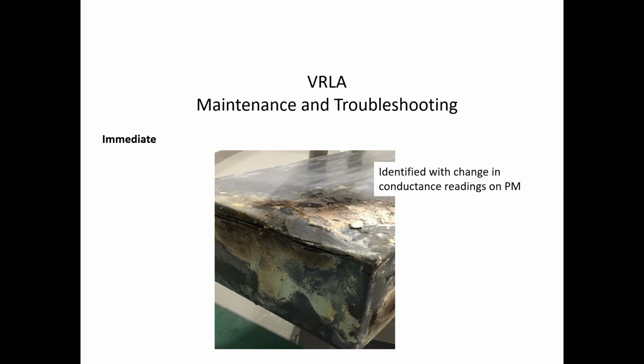You remember I showed you the battery when I showed the valve regulated and the loose cell from the front. Mm-hmm. This is the back of a battery that was installed in, this is also a central office application. I'm not sure what it is about telecom, but we seem to find quite a few issues with those. These very large cells, what they do, they remove them from the steel trays, assemble the steel trays, and then reload the cells. Just because of the weight, particularly when you get pretty high up in these stacks, some of these assembled trays with 3 cells in them are 1,000 pounds. What we think had happened here, they probably unloaded the cell and dropped it and assembled it, somehow cracked it, or it could have been from the manufacturer, but probably unlikely.